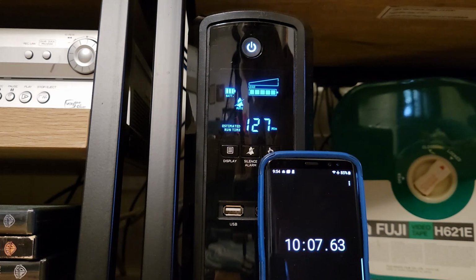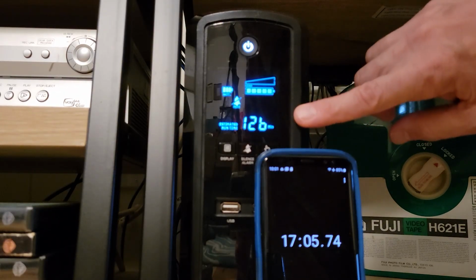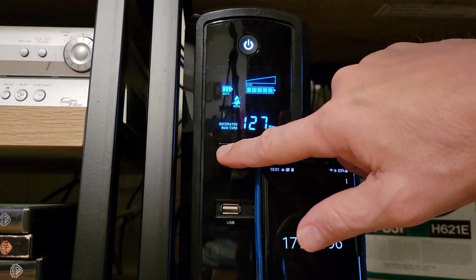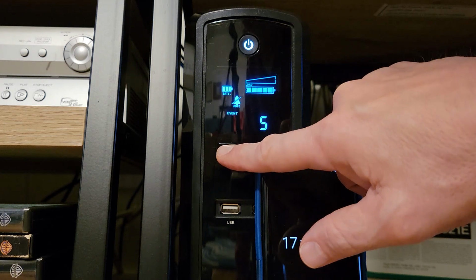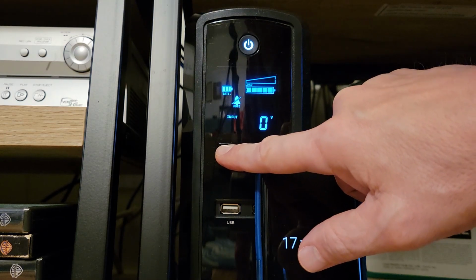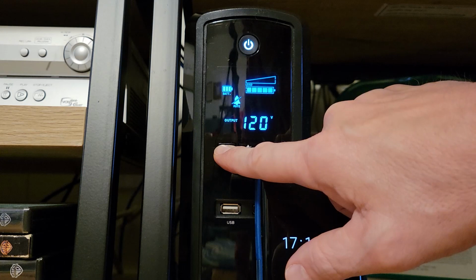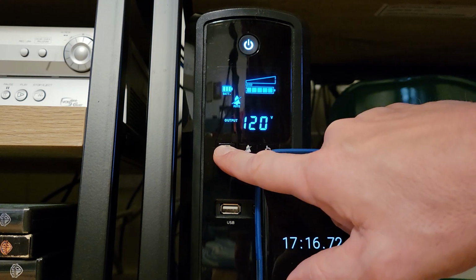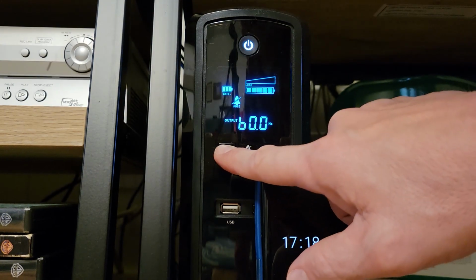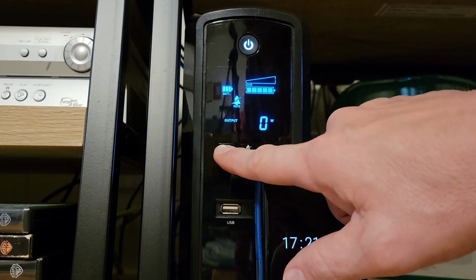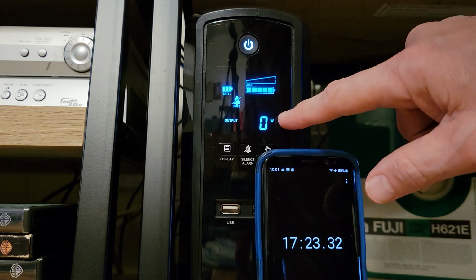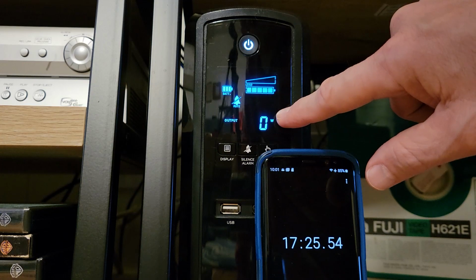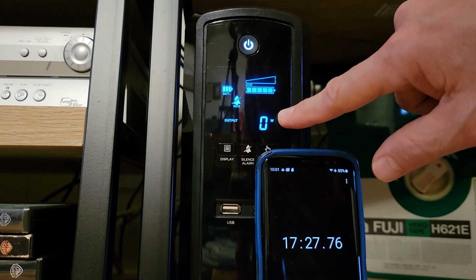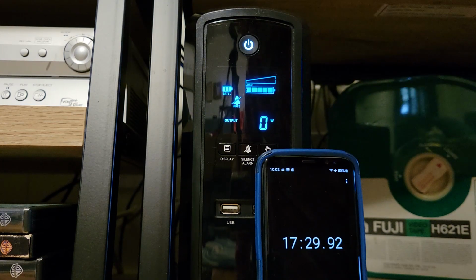17 minutes into the test, we're reading 126 minutes left on the battery. This is event 5 - there's no power coming into the unit. Our output voltage is 120, frequency is 60, output power is below 1 watt. We're not drawing much power at all with the Wi-Fi router and internet switch.